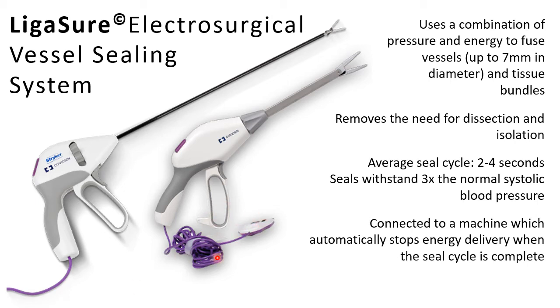The handpiece is connected to a machine through a plug, and on that machine you can adjust how much electrical energy is transferred into the end of the handpiece. For example, if you are ligating or cutting very thick tissue or very thick mesenteric fat, you can increase the level of cutting power; you can also decrease it for friable areas. This equipment is believed to decrease procedure time, the potential for blood loss, and the length of hospital stay for patients. It is used in human surgeries and is now commonly used in veterinary surgeries as well.